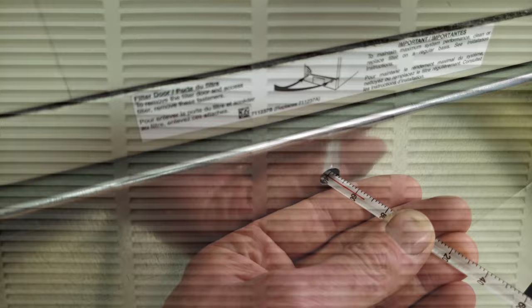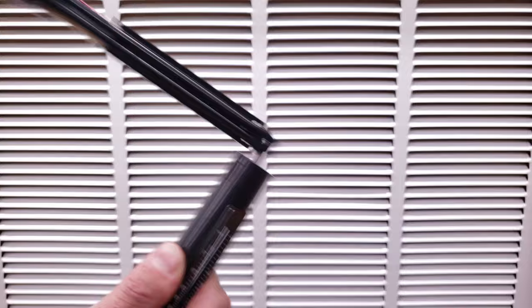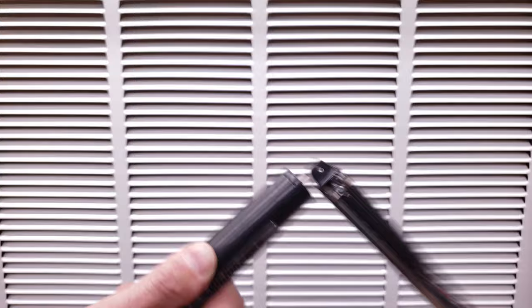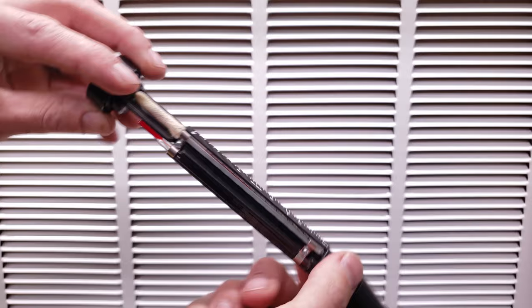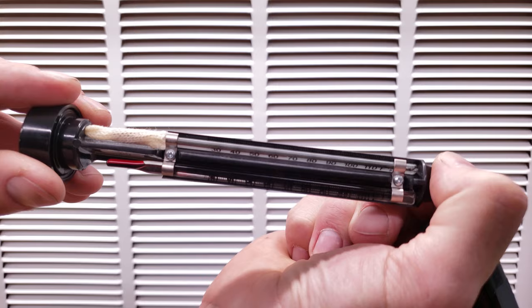Here's our sling psychrometer, and you're going to need to wet the sock right here. I was rotating this ahead of time before I even started recording, but we should be pretty close. You normally have to rotate this for about two minutes in order to get a good wet bulb temperature reading, so you need the evaporation effect on the thermometer. Let's see where we're at right now. We should be right around 65 or so, and if you can see between 60 and 70, we're right at about 65 and a half, almost 66. That's our wet bulb temperature.